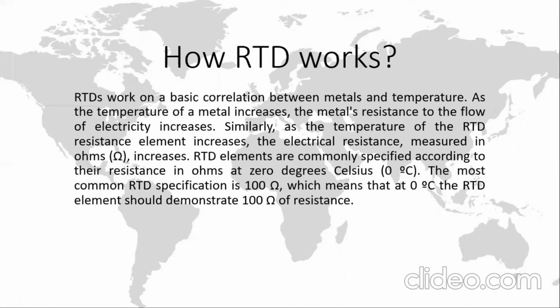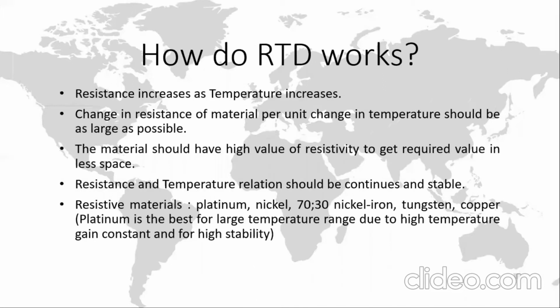RTDs are commonly specified according to their resistance in ohms at 0 degrees Celsius. The most common RTD specification is 100 ohm, which means that at 0 degrees Celsius, the RTD element should demonstrate 100 ohm of resistance. Resistance increases as temperature increases. Change in resistance of material per unit change in temperature should be as large as possible.